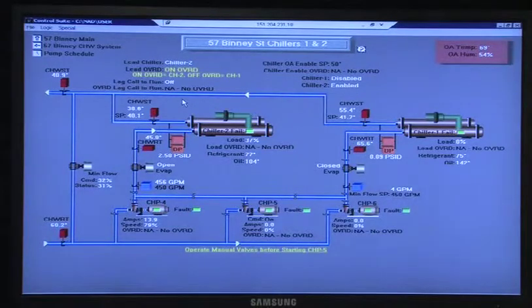So normally you'll be more concerned that if the lead chiller is running and the temperature is like 5 degrees above set point, it's gonna call on the lag chiller. And if the lead chiller is running and the demand on that chiller is above 95% for like 20 minutes, it's gonna call on a second one. So that lag call to run point will turn on and it will tell you that, hey, it's looking for a lag to run.